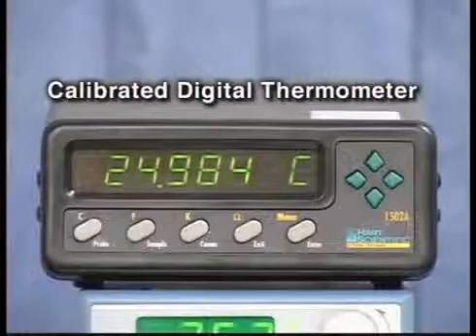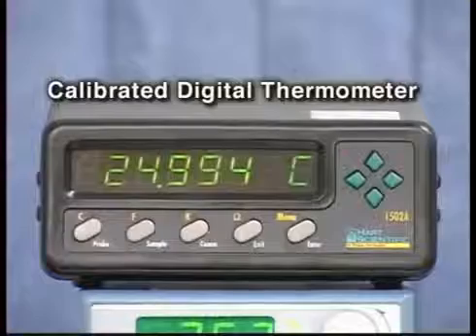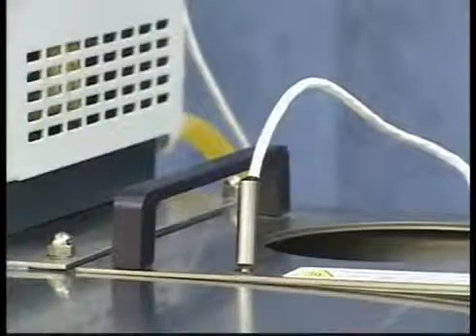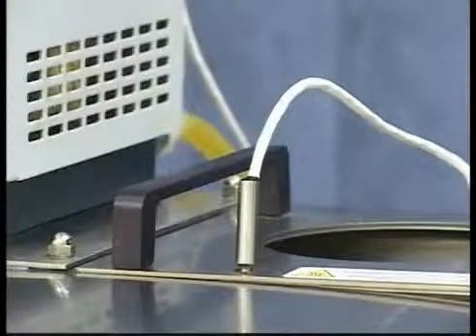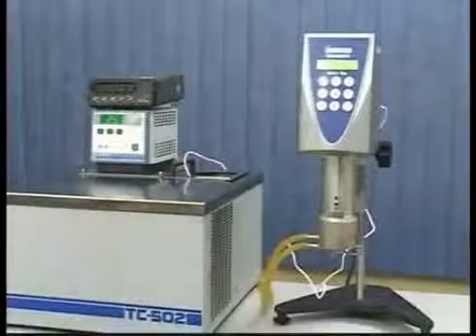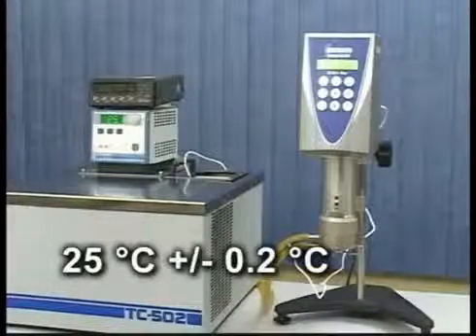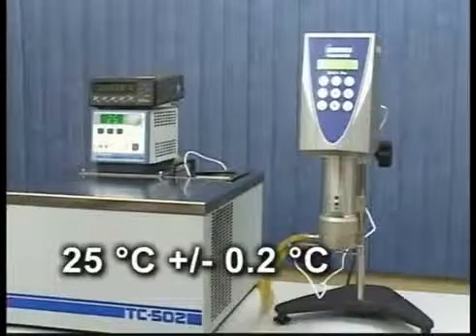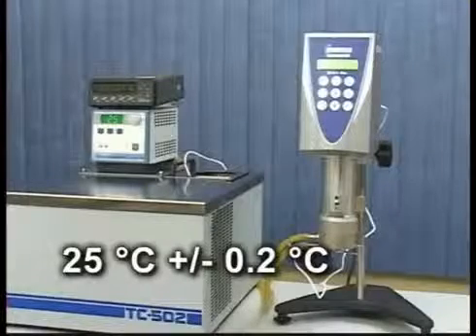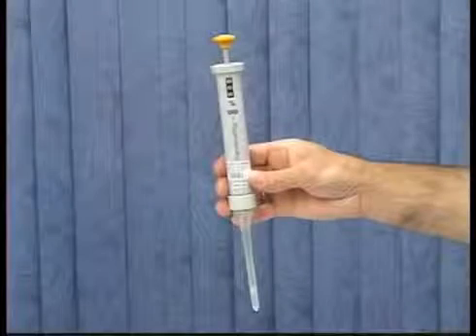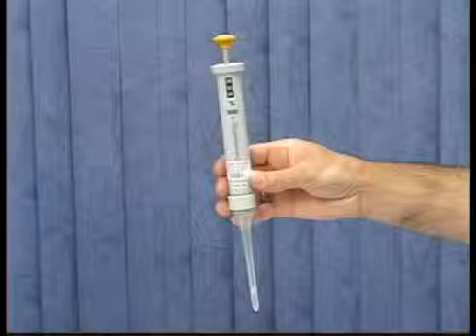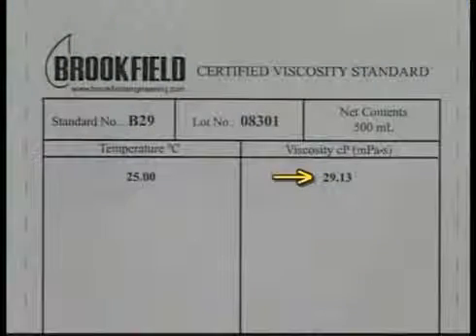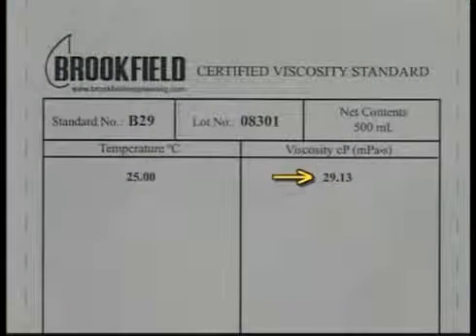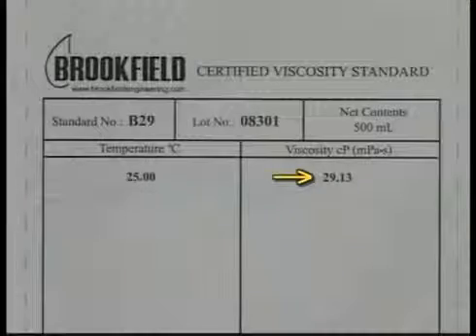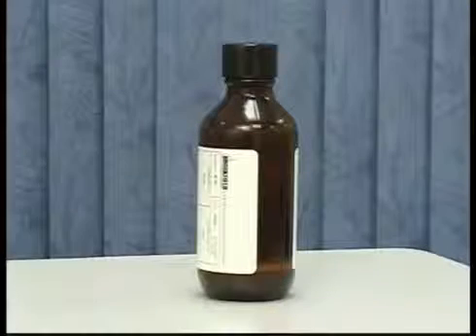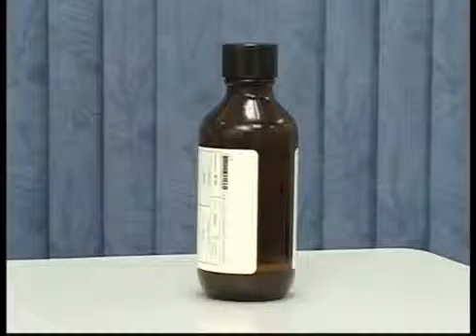To ensure proper temperature equilibration and accuracy, use a calibrated digital thermometer in the temperature bath. Temperature should be controlled at 25.0 degrees centigrade, plus or minus 0.2 degrees centigrade. The thicker the fluid, the longer it will take to equilibrate. For the 29.13 centipoise value mineral oil fluid we are using, this should take approximately 10 minutes or less.